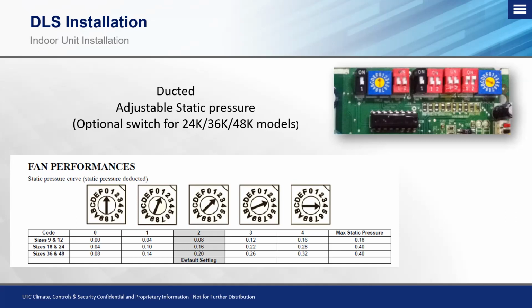And then finally, on our larger sizes, such as the 36 and the 48, our default setting from the factory is 0.2 inches of static, and the maximum that we can push out of that as well is going to be 0.4 inches max. Okay, just something to keep in mind on there. This also can be done from our wireless handheld remote controller. For those of you that have attended the advanced operation class where we went in and adjusted fan speeds after a set point, that same menu is where we can get into for the ducted style units and the vertical air handling style units to go in and adjust for static pressure to meet the certain application that we're dealing with.